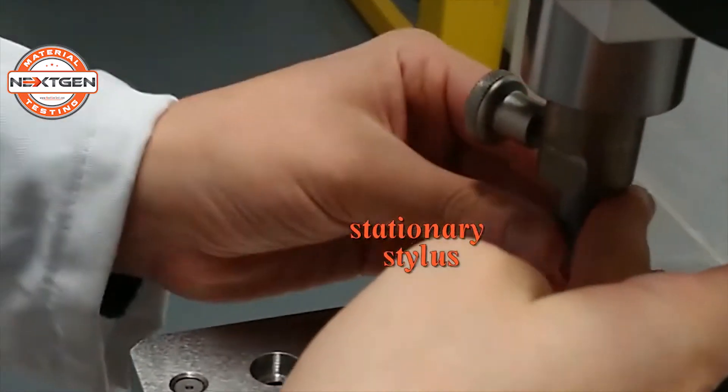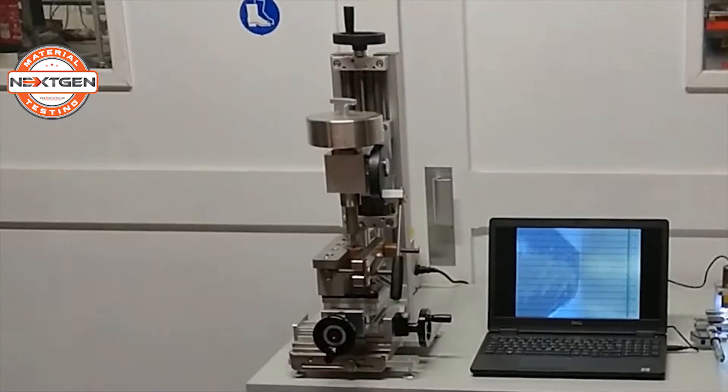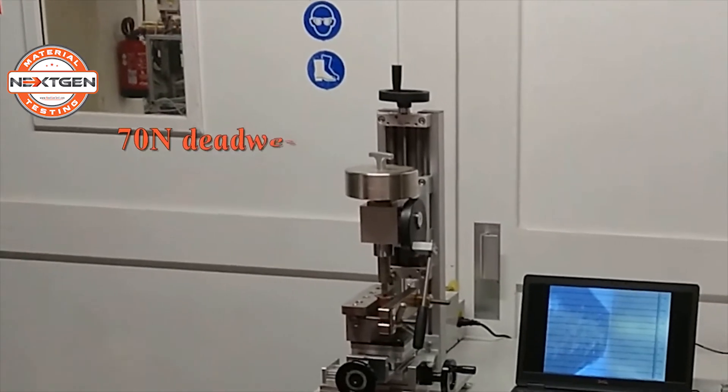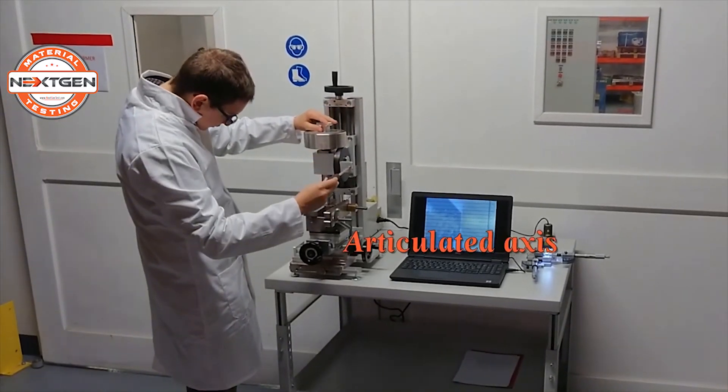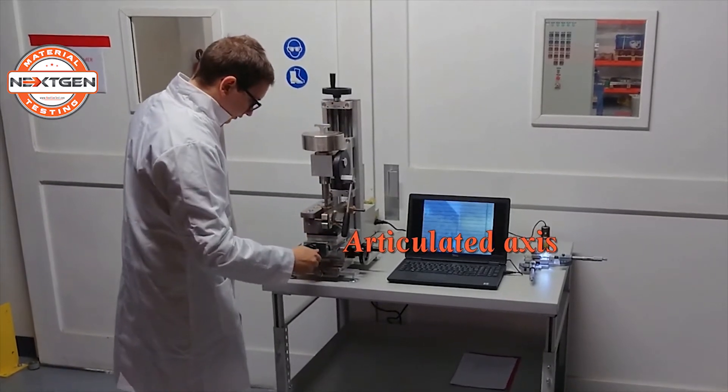The device comprises a stationary stylus and a 70 N dead weight placed on top of the stylus. An articulated axis allows the user to place the stylus on the specimen.